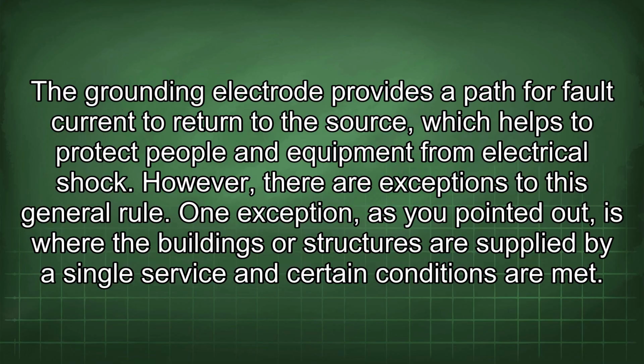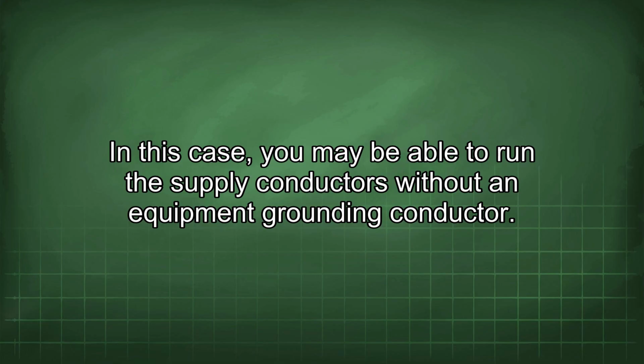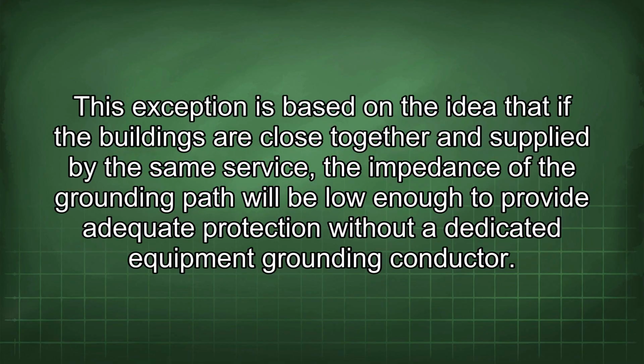One exception, as you pointed out, is where the buildings or structures are supplied by a single service and certain conditions are met. In this case, you may be able to run the supply conductors without an equipment grounding conductor. This exception is based on the idea that if the buildings are close together and supplied by the same service, the impedance of the grounding path will be low enough to provide adequate protection without a dedicated equipment grounding conductor.